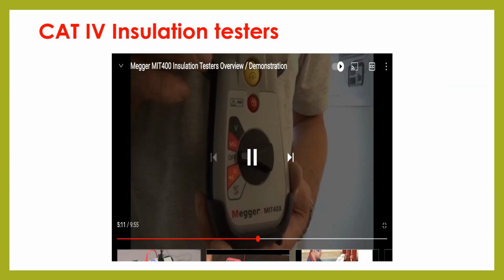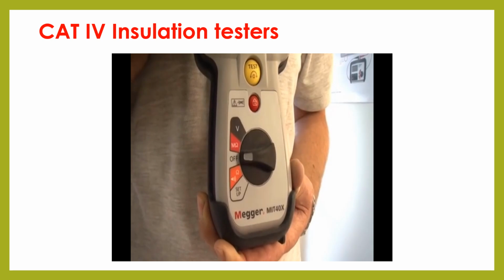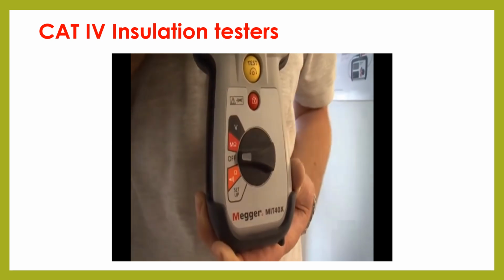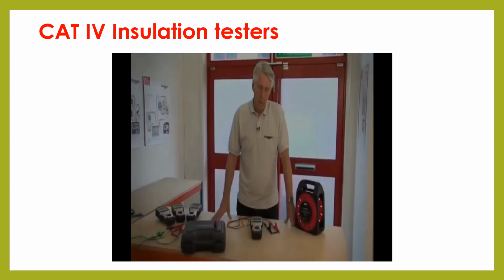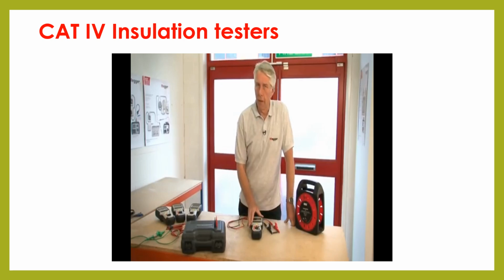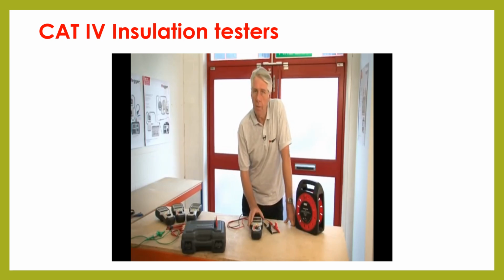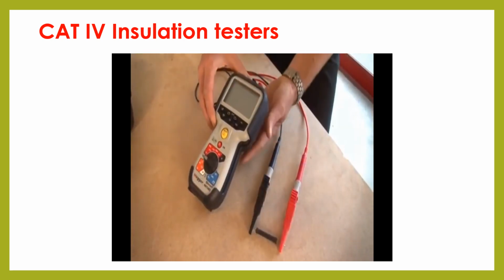It has true RMS AC and DC voltage measurement facility as well. Using an MIT 485, what I'm going to do now is a demonstration of the insulation testing, continuity testing with a buzzer, and I'll also show you the test inhibit, which occurs if the product is inadvertently connected to a live supply. For the purpose of demonstrating the insulation test, I've connected a 25 megohm resistor between the red and black crocodile clips. So first of all, we select the test voltage.